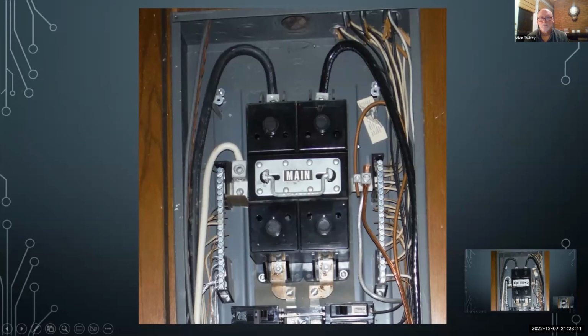This is probably the grounding electrode conductor. This is an equipment grounding feeder to probably a higher amperage appliance circuit. This aluminum, I'm assuming, is probably a water pipe bond, and it's double tapped here where it shouldn't be, but that's what these things are. That's an older panel. Pull out fuse.